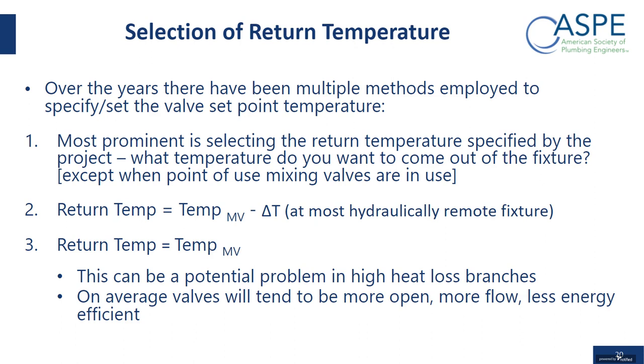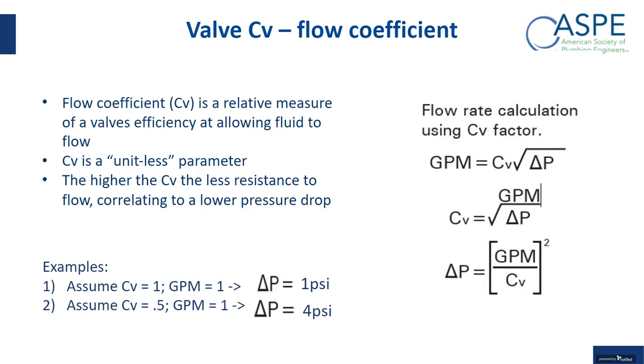The potential downside of that is with a fixed balancing valve that has a 10-degree range of open to close, if you have heat loss approaching 10 degrees Fahrenheit or higher, that valve will be full open all the time. And if a majority of your valves are full open, then you're basically going to have issues with balancing because you're going to be producing a lot more flow than you need. The other problem with doing it this way is all these valves on average are going to tend to be more open. So if they tend to be more open, there's going to be more flow. If there's more flow, then it's going to be less energy efficient. So it's just something to consider. Again, I prefer selecting the temperature based on whatever return temperature you're looking for.